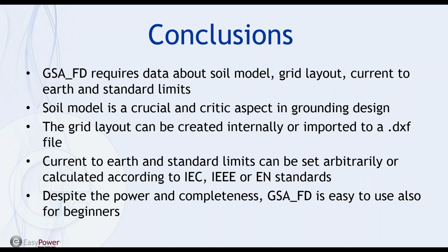The current to earth and the standard limit can be set arbitrarily or calculated according to IEC, IEEE, or EN standards. In particular, we used the IEEE Standard 80 2013 edition. Despite the power and completeness, GSA FD is easy to use also for beginners. Of course, GSA FD, as other advanced modules, requires specific knowledge, but not necessarily an expert user. Expert users and researchers can always appreciate calculation capabilities and rigorous algorithms.